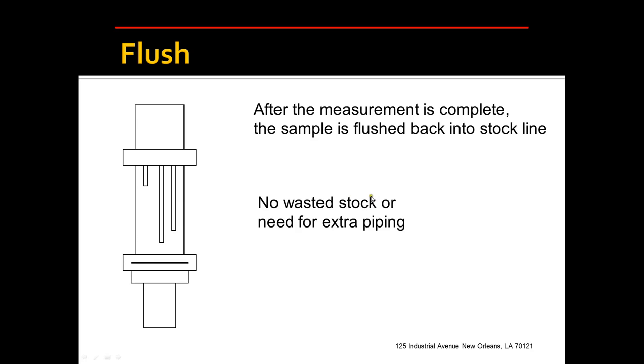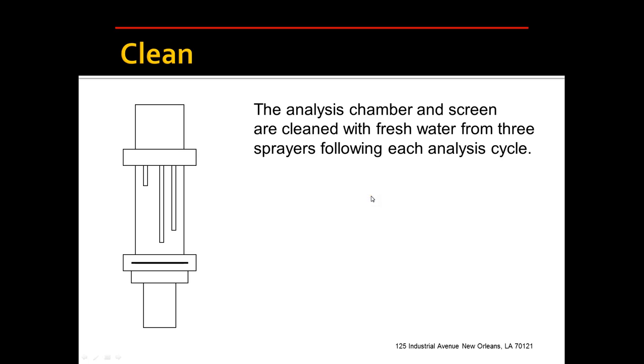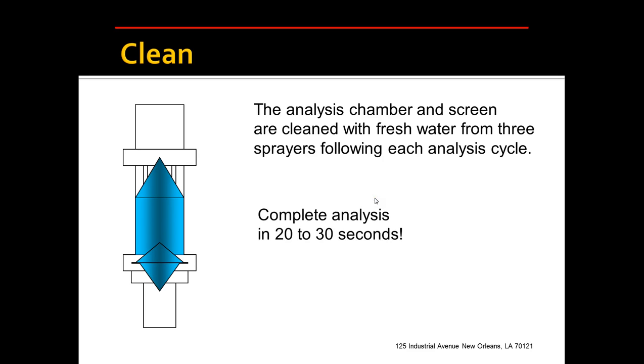At the same time that that's happening, we also turn on a variety of different flush points. There are 3 flush points, one below the screen, one above the screen, and one at the top. And we turn all those on and basically clean your entire system. And we can complete an analysis in roughly 20 to 30 seconds.